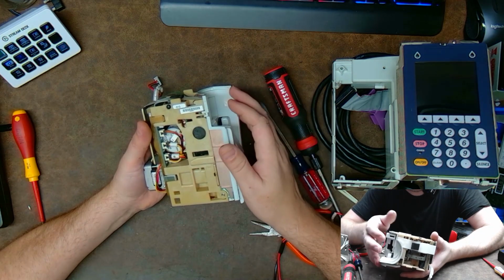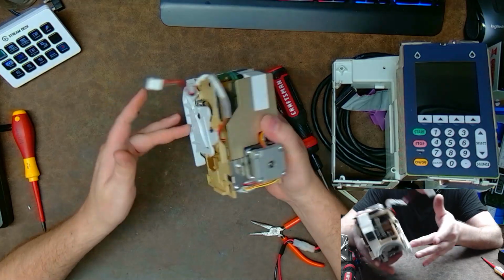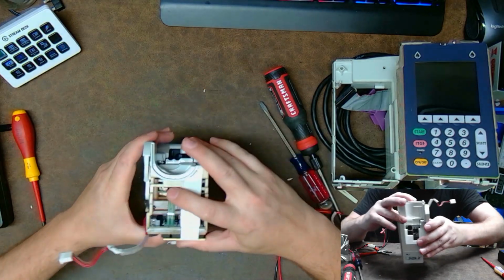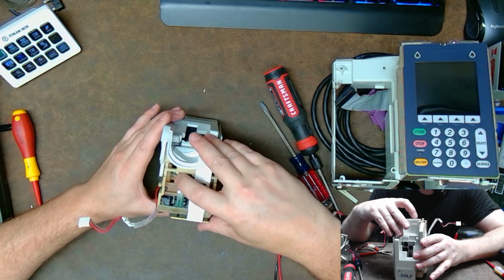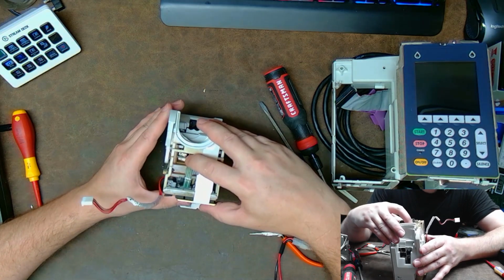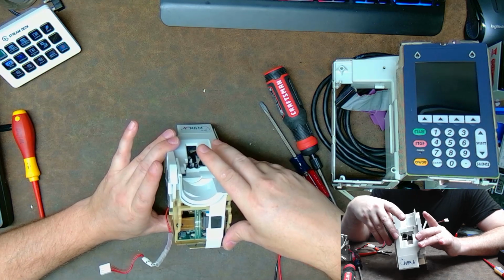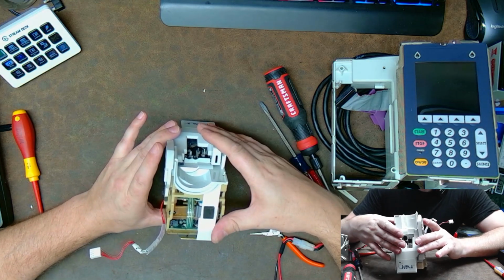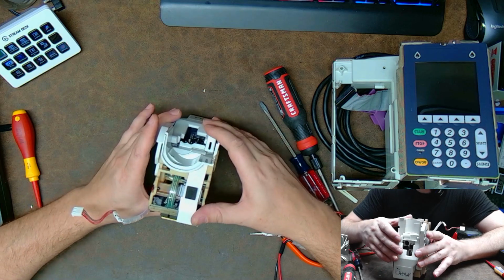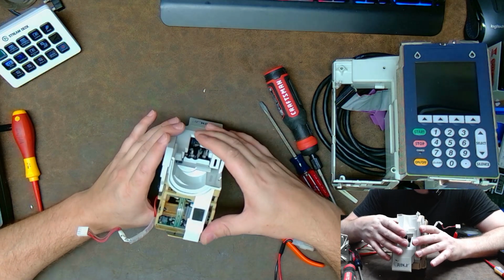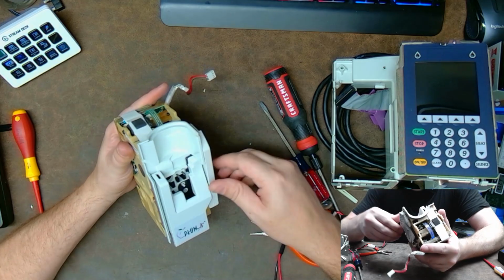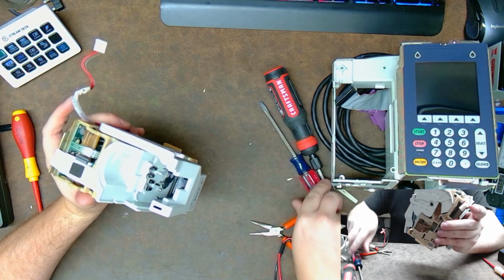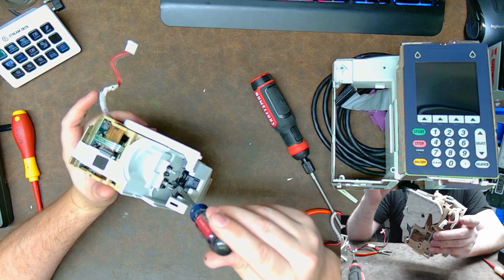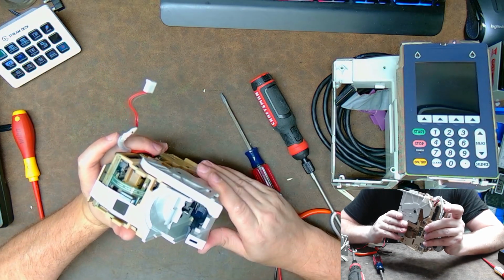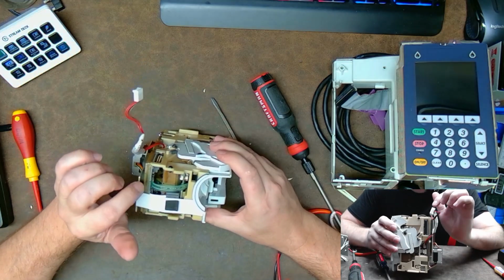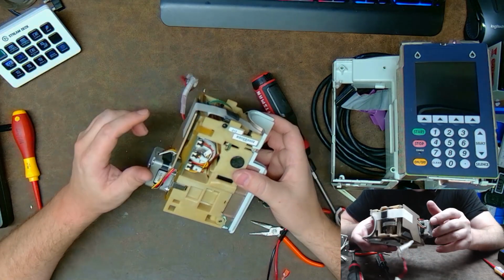And you're going to be driving them off this card that's in here. And in order to adjust that card, there's a series of tiny little potentiometers up here at the top. And so those are going to be obviously your occlusion pressure. They're going to be adjusting probably the pulses, the amount of pulses that are given for a certain quantity. And let's see, come on. This diaphragm is right down here. You can barely see it, the rubber diaphragm right there. That senses your occlusion pressure, so you're going to be adjusting that gain as well on some of those tiny little potentiometers.